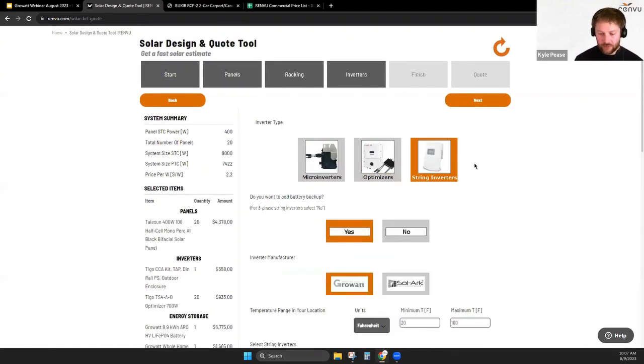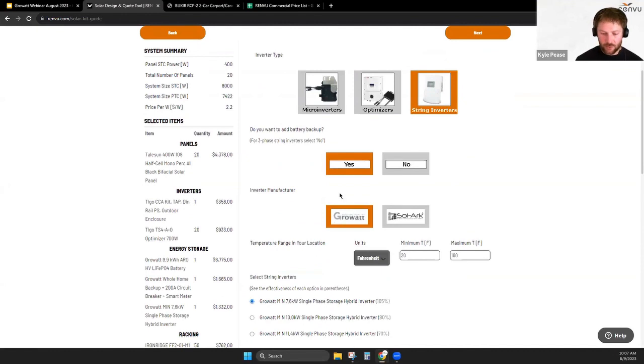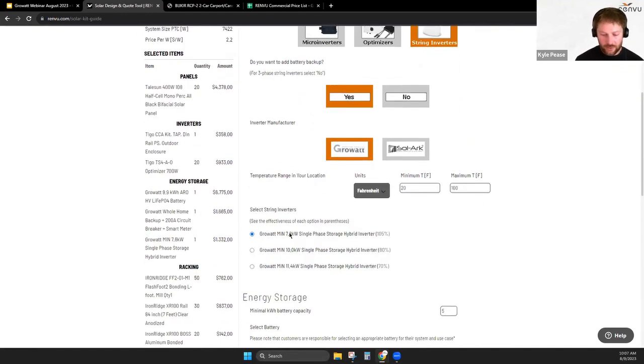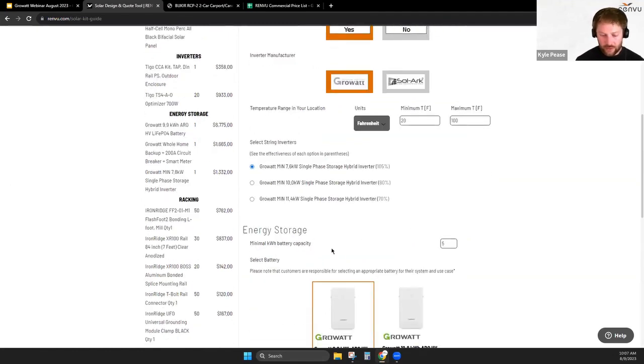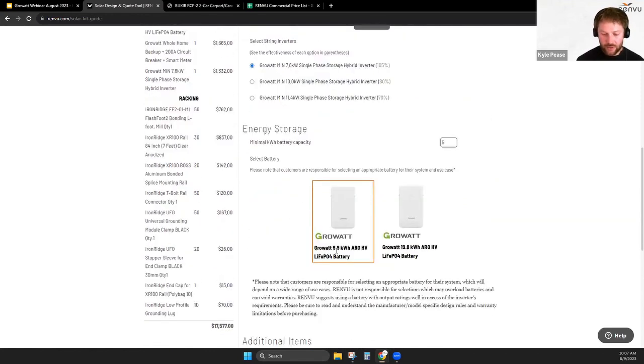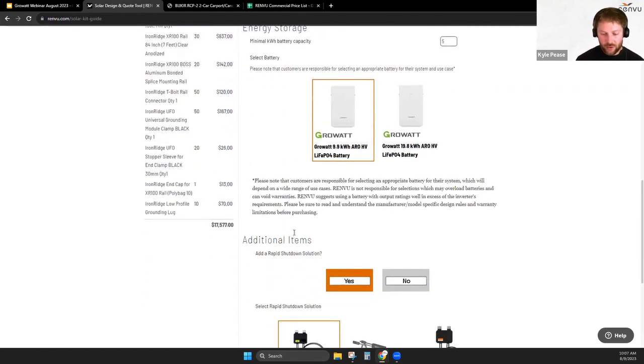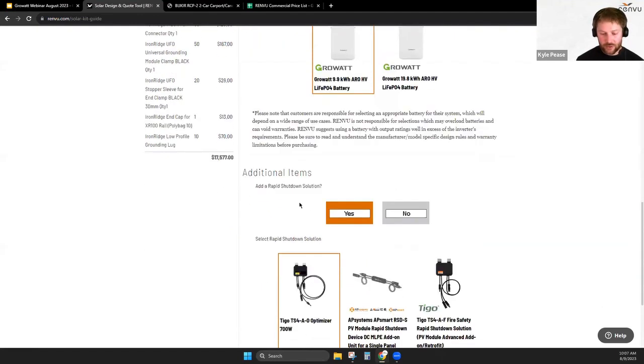If we jump over to string inverters, of course, we have Growatt, and if we add their battery backup, we can select a 7.6 kilowatt hybrid inverter there, that would be basically a fully loaded 200 amp panel, and their 9.9 kilowatt hour battery. We could then compare costs for that versus some other options to see what would make the most sense for us. Also, rapid shutdown is on this page too.